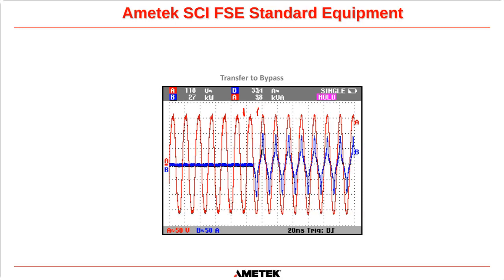And we can see the red sine wave here, this is the sine wave of the inverter, and this is the sine wave of the bypass applying load, because we're actually monitoring that on the output of the system. So you can see that no blip, dip, or anything happened to that voltage when the transfer took place. And that's exactly what we're looking for. If we'd seen that this whole portion of the sine wave had gone missing when the transfer happened, then we would know we have an issue. If we saw that sine wave went straight over to there, then we have a whole pulse missing, and that's not good. We would troubleshoot further to see what is happening. But that is why we capture the transfers with an oscilloscope, so we can prove to you that the system transferred seamlessly.